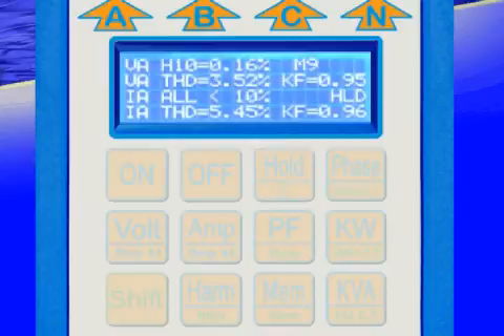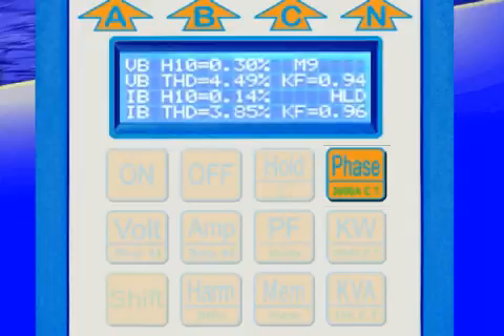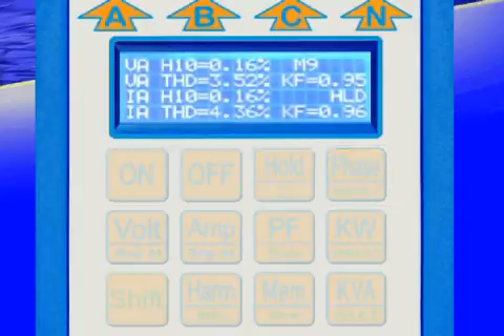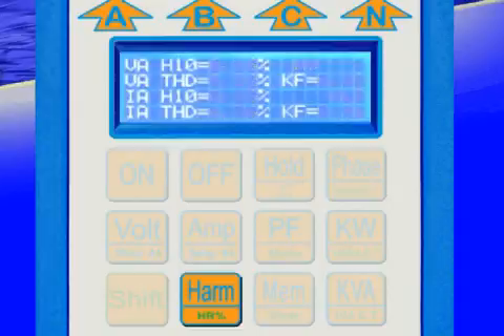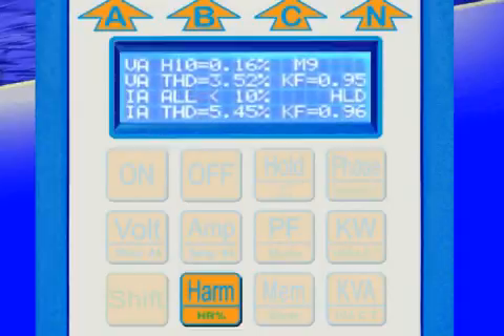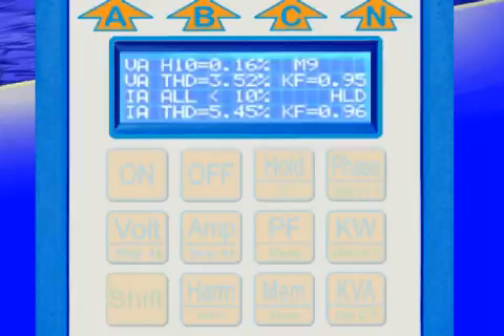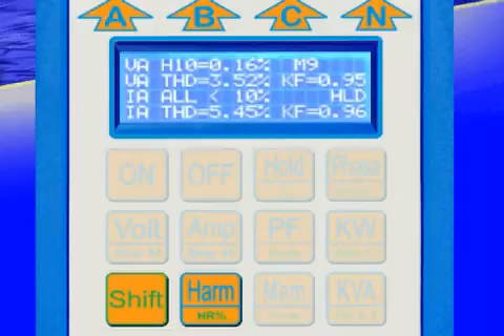To view other phases, hold down the phase key until the phase you'd like to view is displayed. To scroll through harmonics that are above a certain percentage, hold the Harm button. This will only display values that are out of IEEE standard magnitudes. If you'd like to cycle through harmonics individually, press and hold Shift and then press the Harm button to scroll sequentially through each individual harmonic.